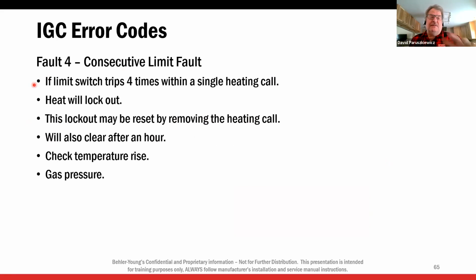If we trip the limit one time in a cycle, it'll clear. If we trip the limit 4 times in one heating call, we're going to lock the unit out. All right. So again, if I trip the limit 4 times in a heating cycle, the unit's going to lock out. So if I have that blower with the manual reset limit and I put the auto reset limit in thinking it's going to cure my problems, it's not. We still have to correct that problem. All right, so 4 consecutive limit trips, heat will lock out.